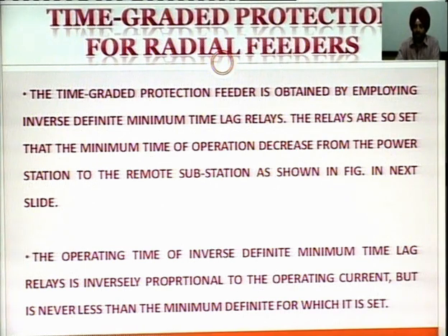So this is the point to note. The relays are set so that the minimum time of operation of a relay decreases from the power station. So from the power station the relay time decreases up to the remote substation, as shown in the figure.